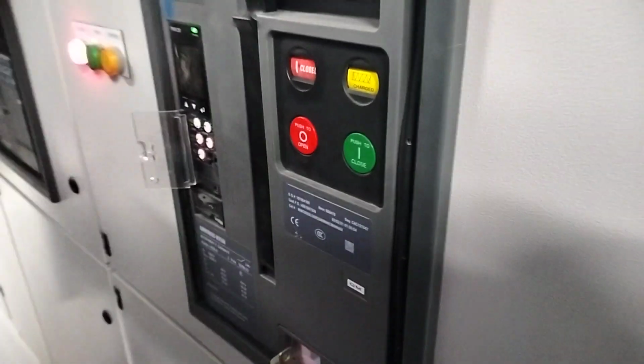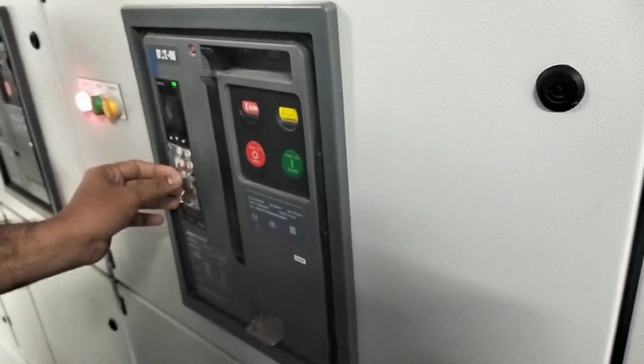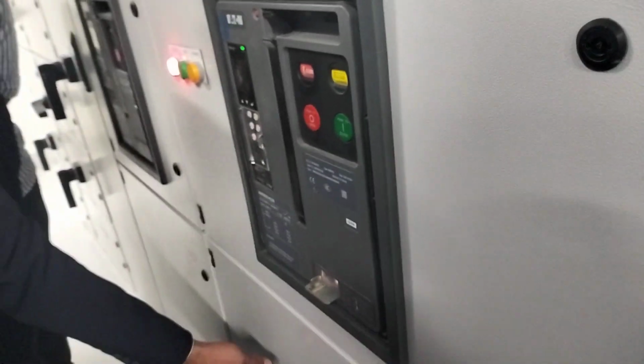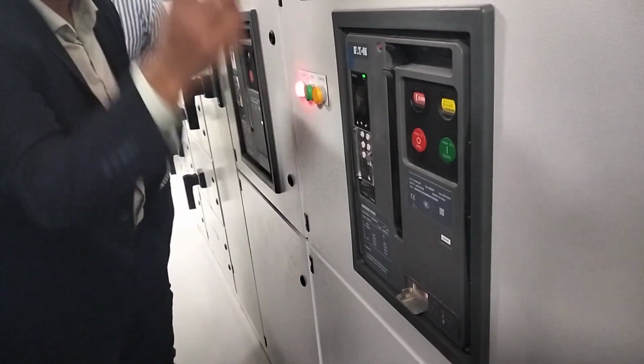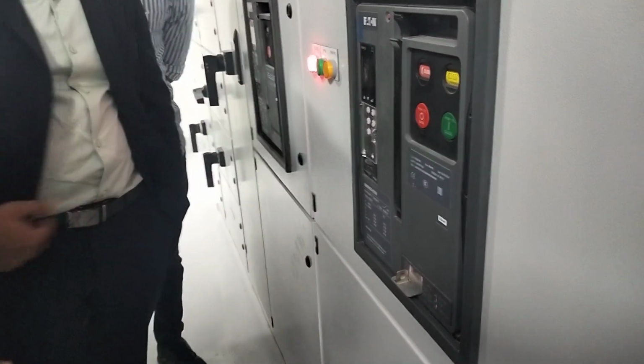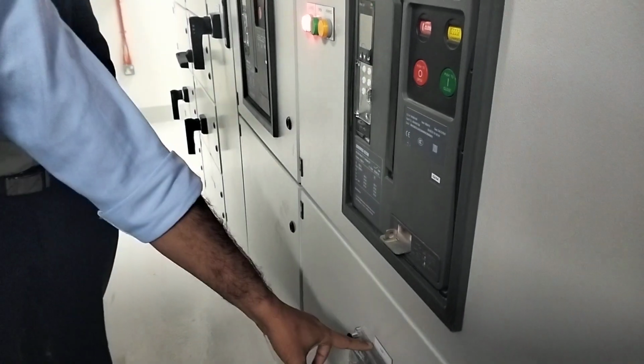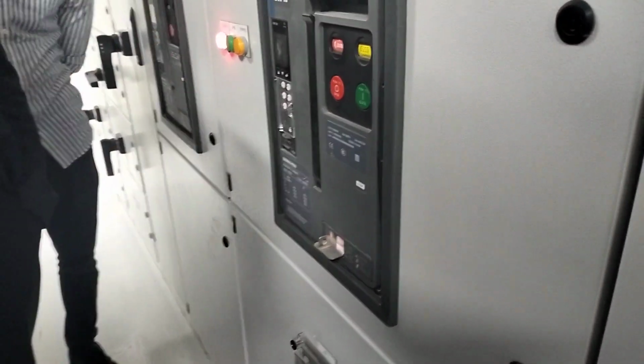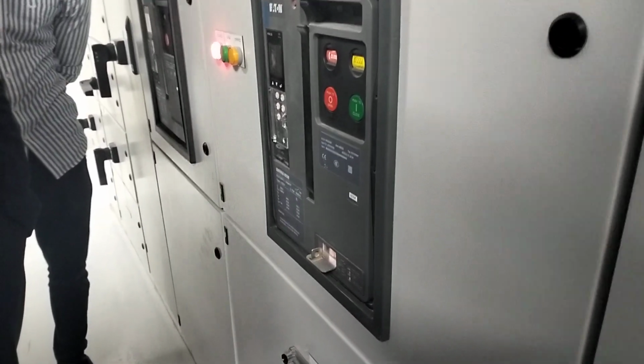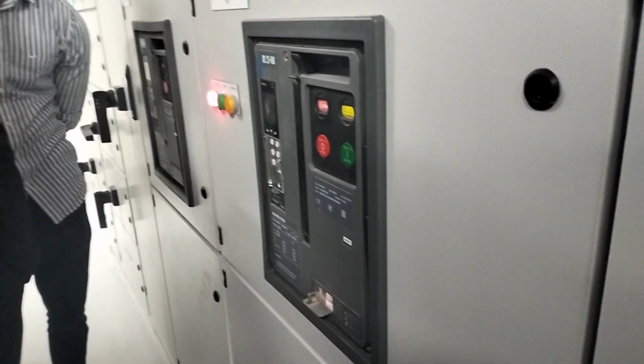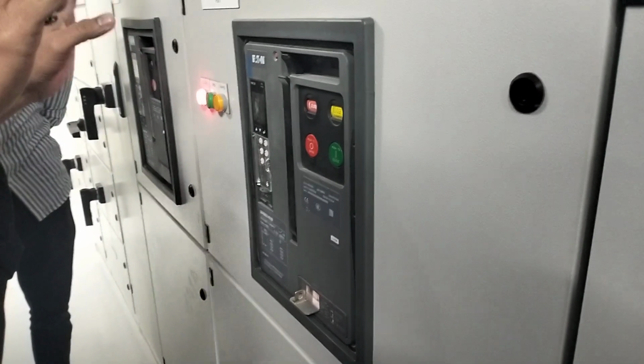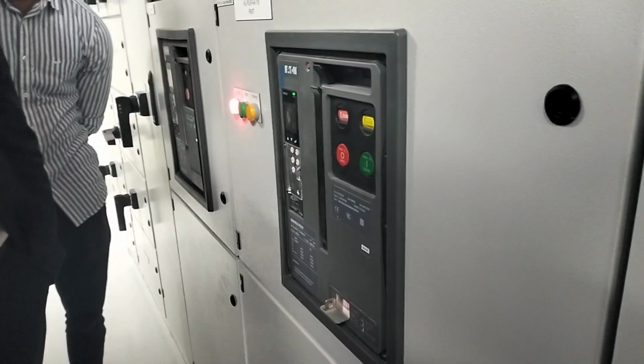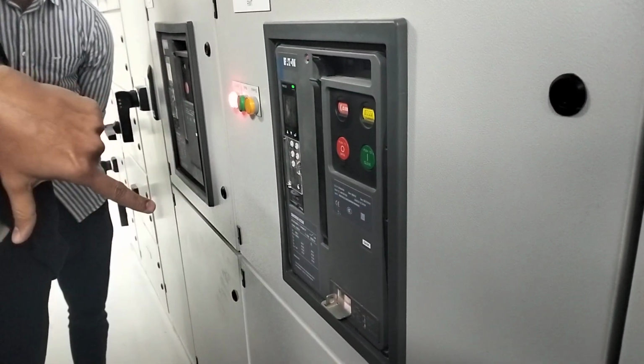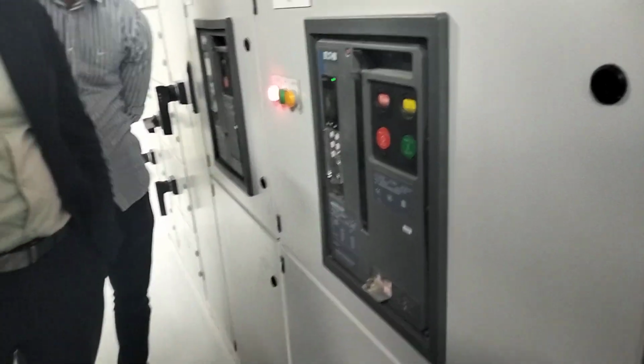So we have one protection, which is earth. We have low voltage and high voltage protection also. This protection is for the transformer. If any earth fault happens, this is called a restricted earth fault. It will protect from the transformer to the LV incoming side. Any earth fault on this side, it won't act. If you have protection in your panel, it will activate. There is no earth fault protection here, but if any earth fault happens from the transformer to the LV incoming side, it will operate and trip your HT breaker, the upstream breaker.